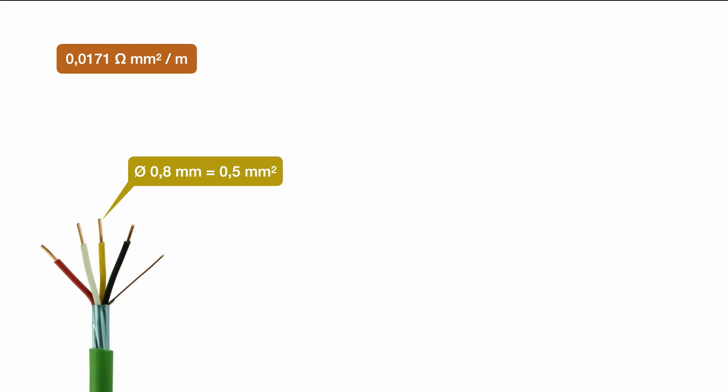In case we want to figure out what's the resistance of one meter of our cable we go ahead with 0.0171 ohm millimeter square per meter and multiply it by one meter and divide it by 0.5 millimeter square, the actual cross-section area of our cable. If you do the math you will end up with a result of 0.0342 ohm because all the other units will just eliminate each other. So that's the resistance of one meter of our cable.